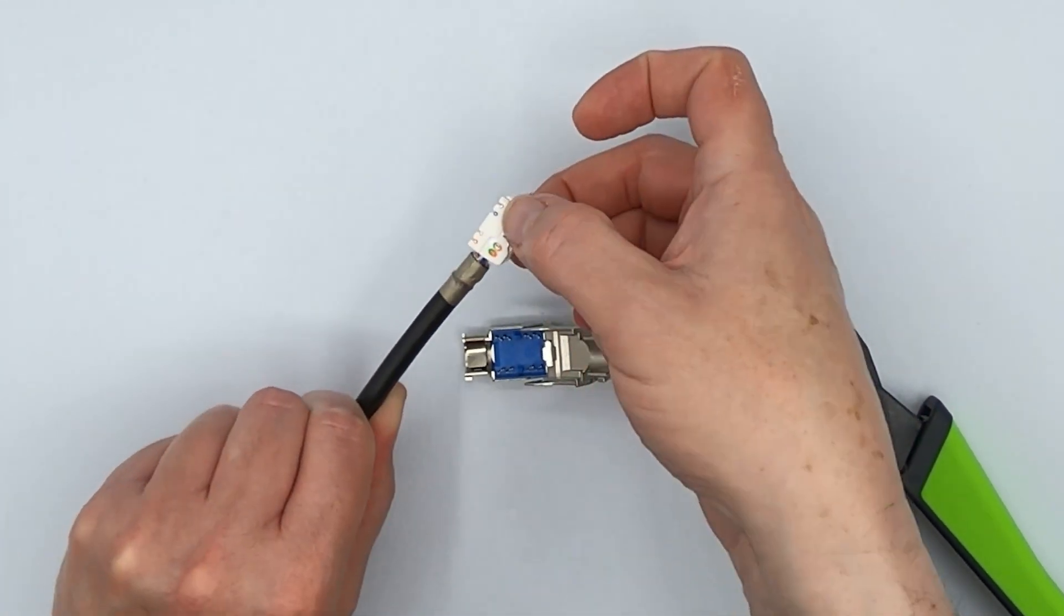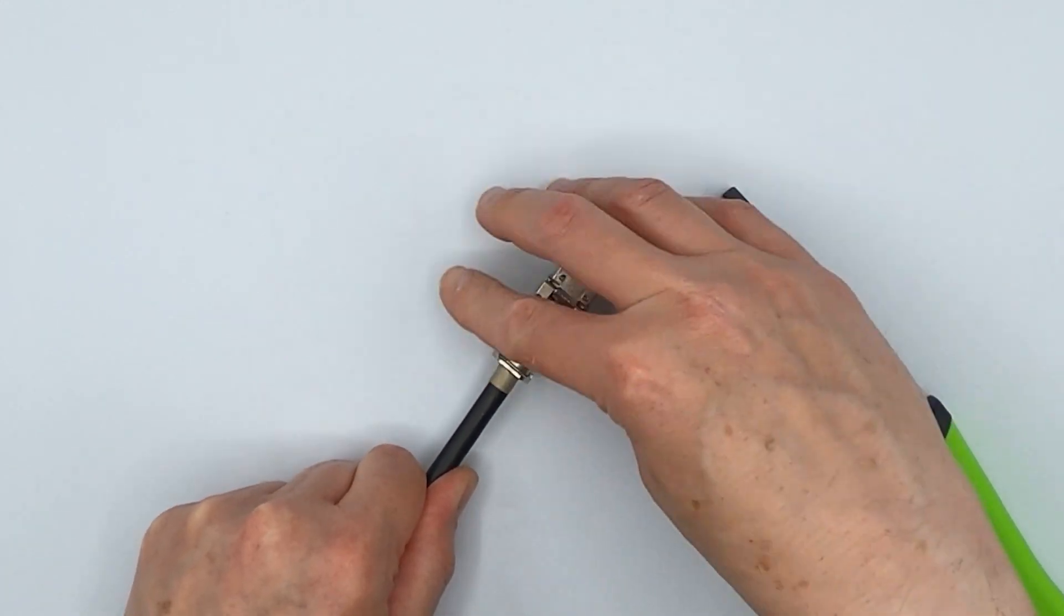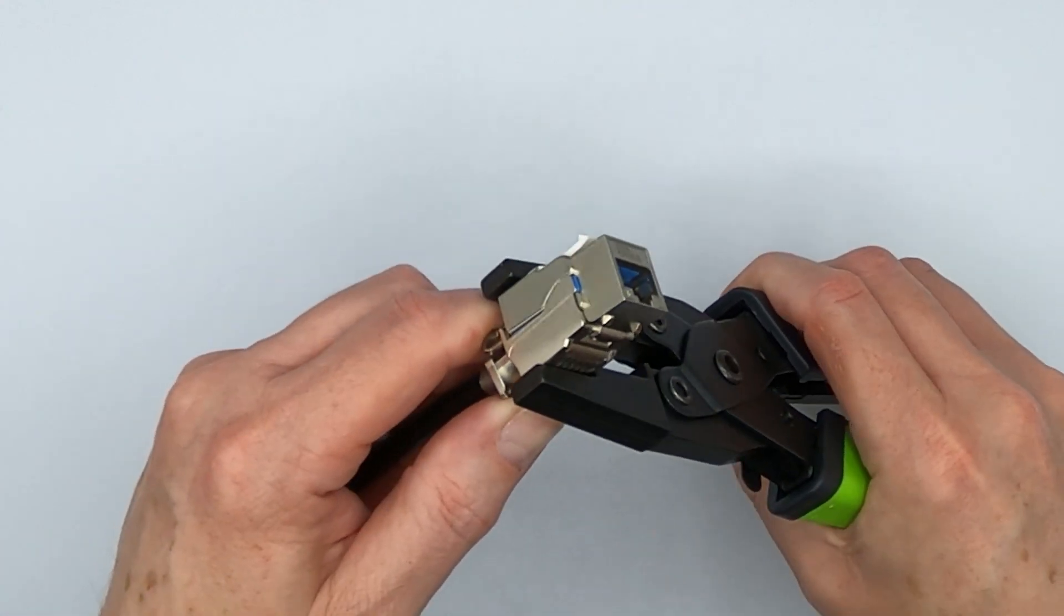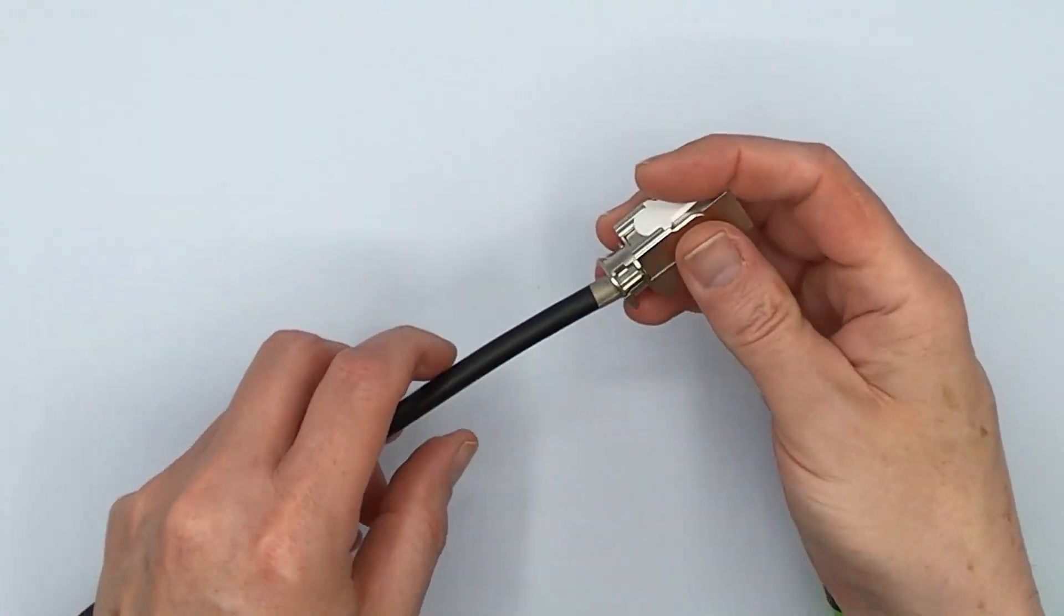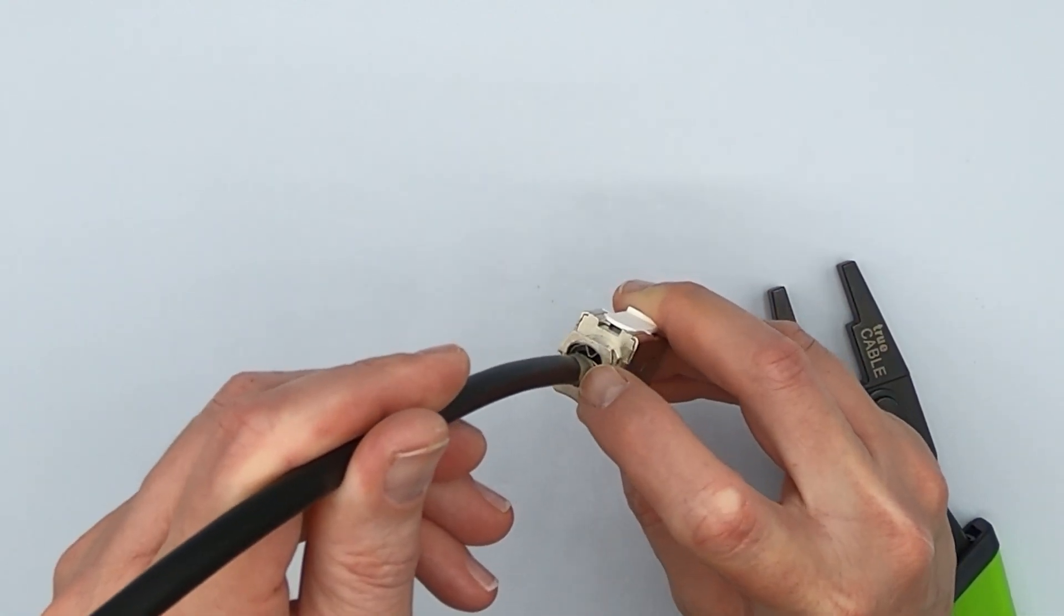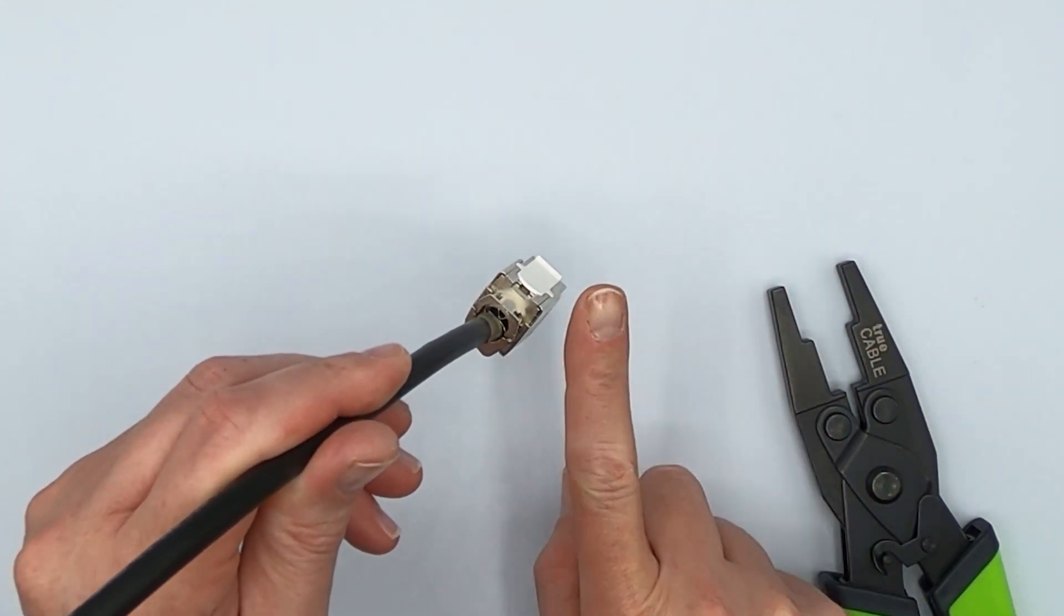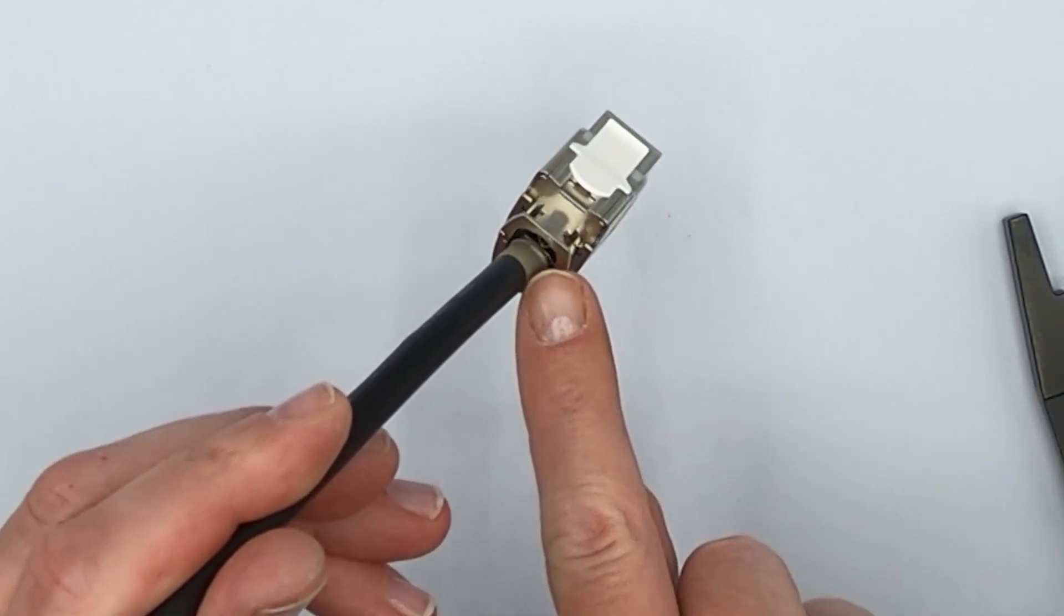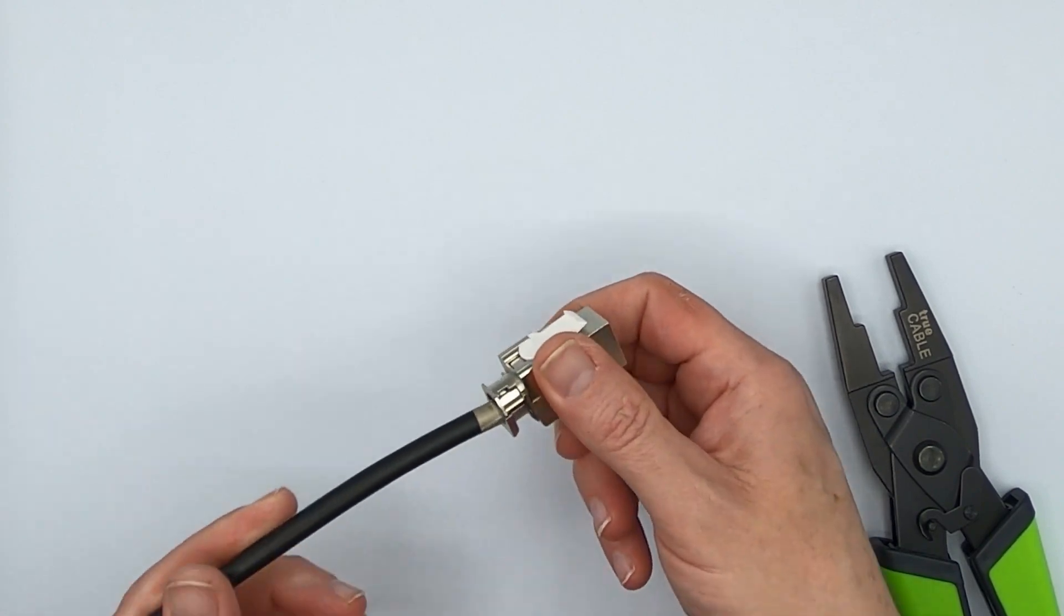And then you've got your conductor holder cap on here. It's already wired up. And you put it into your jack, close it. Use parallel pliers to close this guy. There we go. And now that leaf spring in there is making excellent electrical contact. It's bonding. It's called the process of making a low resistance electrical contact, called bonding.